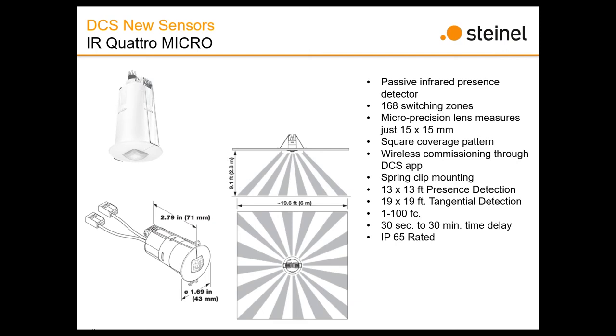But you've got the spring clips there to hold it in place. It is plenum rated, you just stick it right up there. It does not need to be mounted to a junction box or anything like that. It's passive infrared. We know our competitors only give somewhere between 50 and 100 switching zones typically in their top of the line sensors. We like to blow that away by a factor of 10 or 100, but this one only just beats it, 168 to 100, in terms of switching zones.